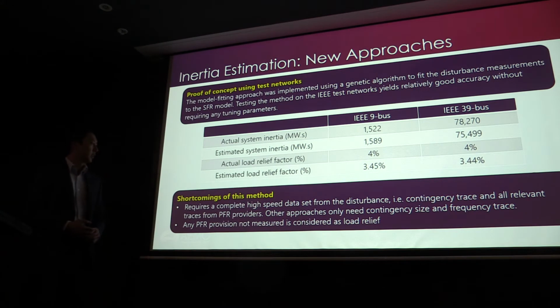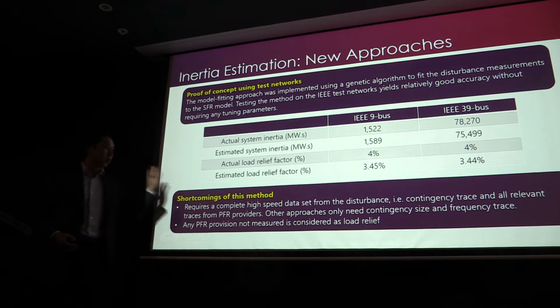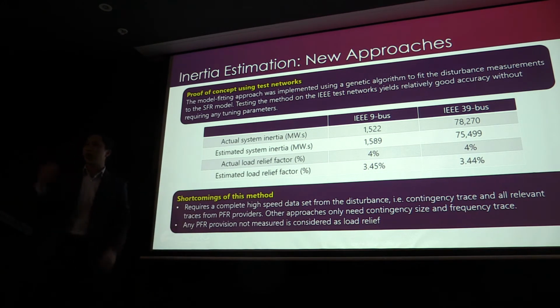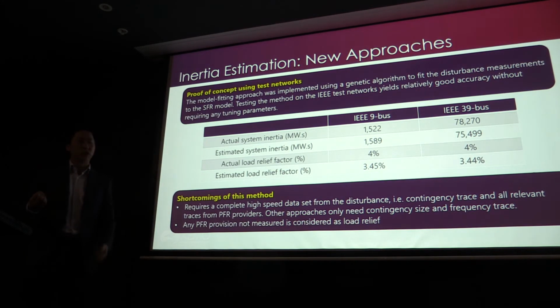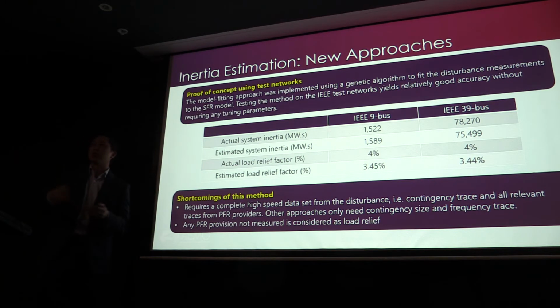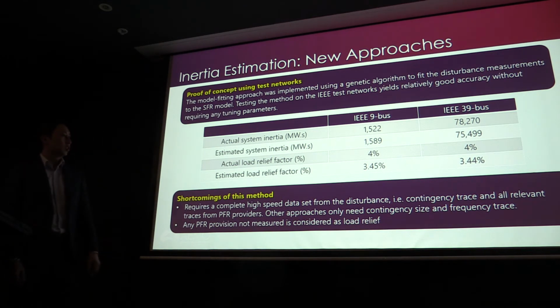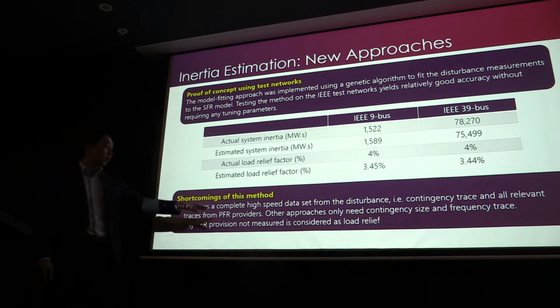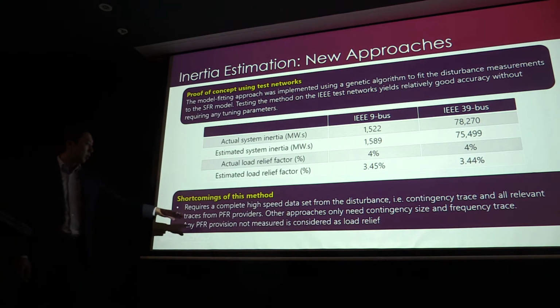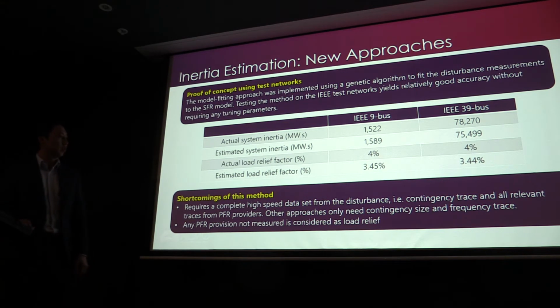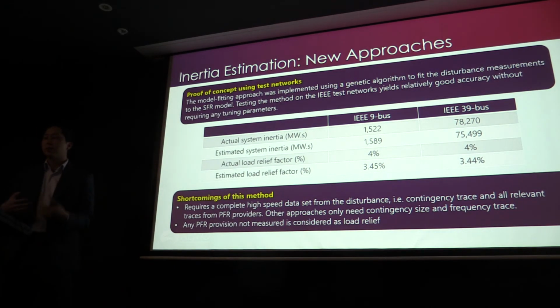Some of the shortcomings, I guess, is that you actually require a complete data set. If some high-speed data is missing, it's more difficult to use unless you try to put in dummy data from past events to simulate that. So you need to have the contingency trace and all of the traces from the PFR providers. If you don't have a PFR provider, then if it's not measured, it's considered as load relief. That's basically the upshot of it. The other approaches only need the contingency size and the frequency trace, but they're potentially less accurate.